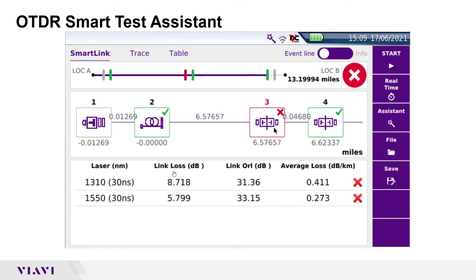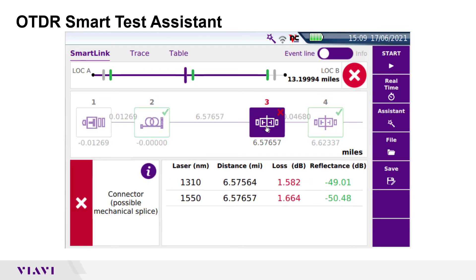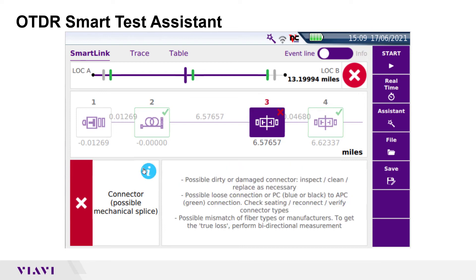The center display shows summary results for each acquisition. Events are marked with a green check or red X based on the pass-fail settings. You can tap on any icon to get detailed results for that event. Results include distance, loss, reflectance, and the event type. Tapping on the information icon provides a list of possible causes for the failure.